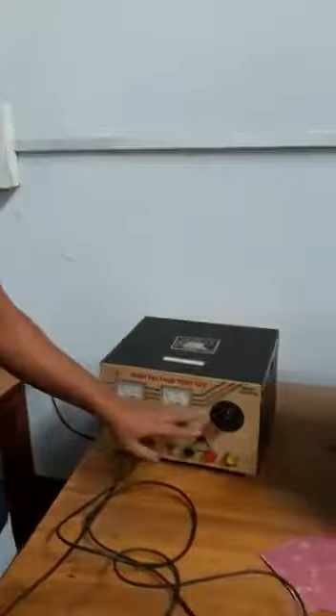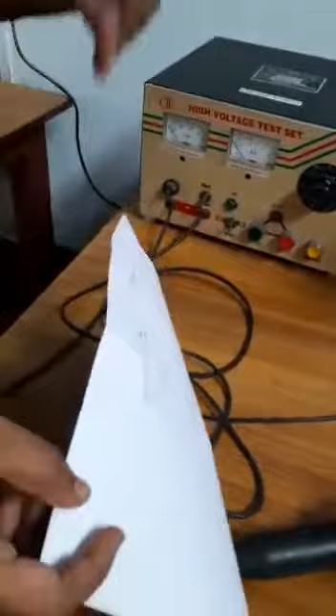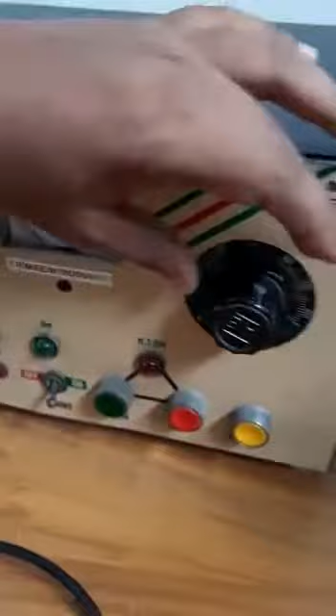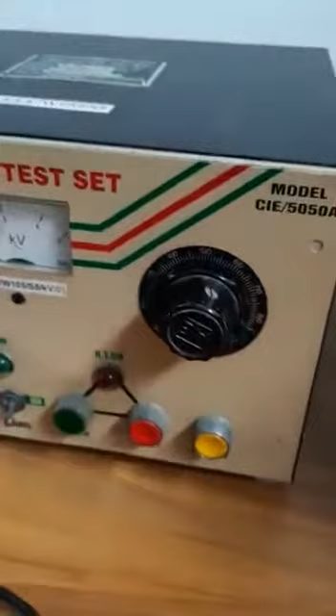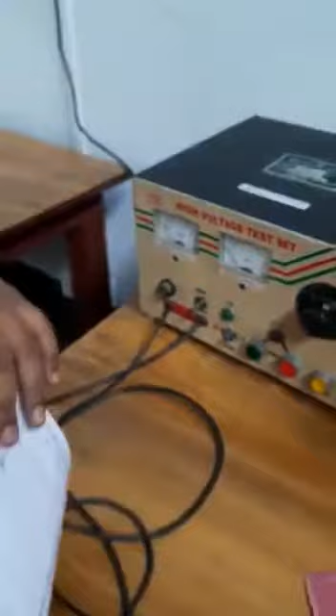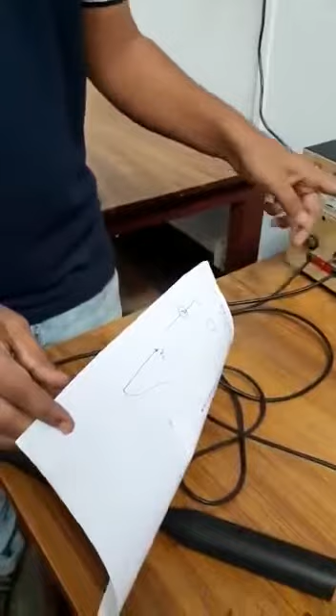The same procedure can be followed for insulating paper as well. You place the paper between the two probes, with these copper heads facing each other, and apply voltage with the variac. At a particular voltage, the paper will lose its insulating property - that moment is the breakdown, measured with this integrating voltmeter. You press the memory switch to capture the reading. If you measure the thickness of the paper with a vernier caliper, you can divide the breakdown voltage by the thickness to get the dielectric strength.